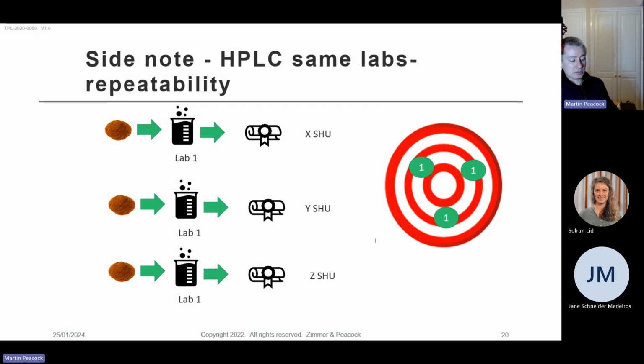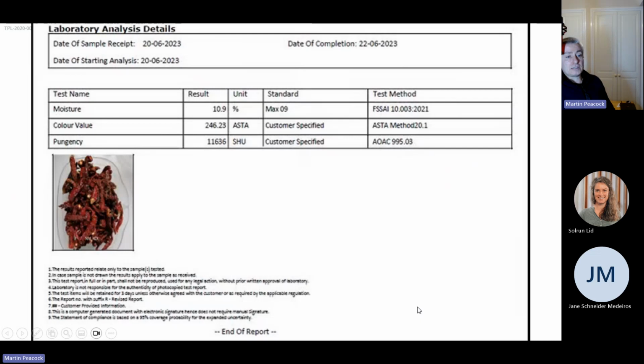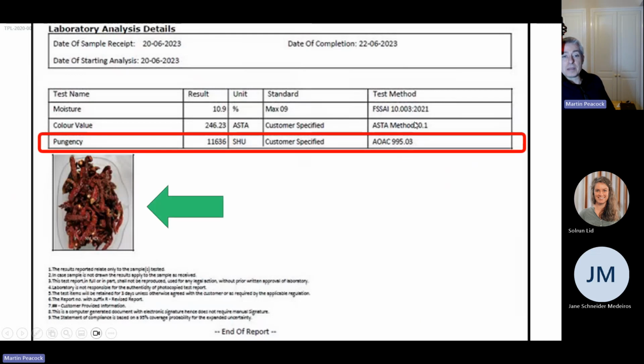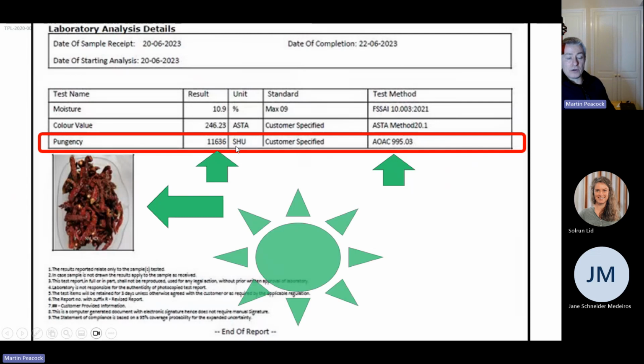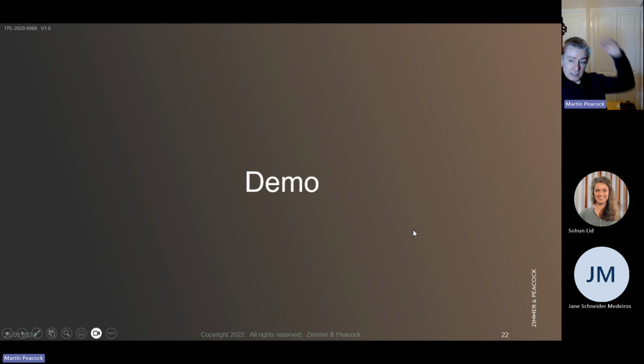No criticism of the technicians, no criticism of the instrument itself. It's just that this is a very heterogeneous sample type, and you have to do multiple tests on it to really understand the range. And that's not happening because it's too expensive and too slow. So you get a certificate of analysis, and they may be running what's called the AOAC method, which is a perfectly fine method, and you'll get an absolute number, but no plus or minus error on it. But with the FoodSense, we do get people to do multiple tests because they can afford to do it and they can do it fast, and we can understand what the true range of these things actually is. Now, what I'm going to do now is I want to be quick.